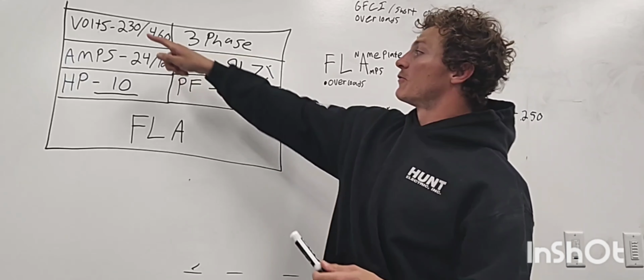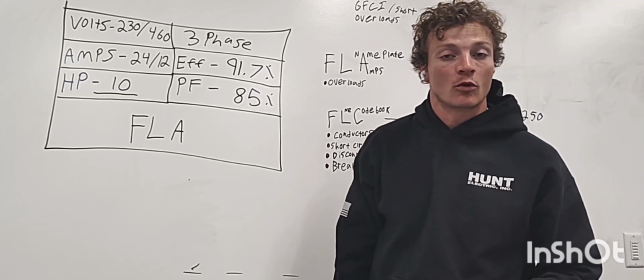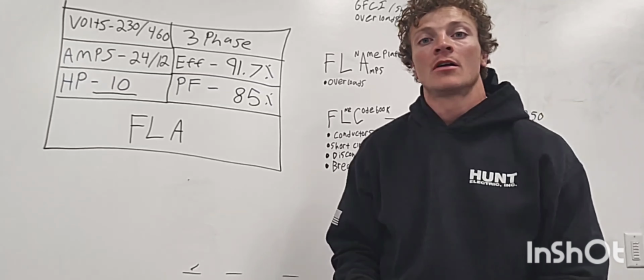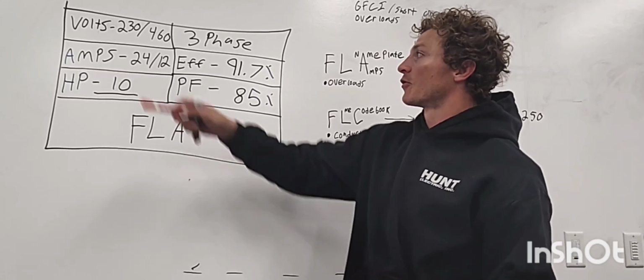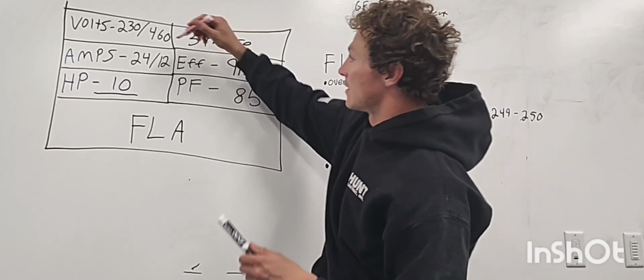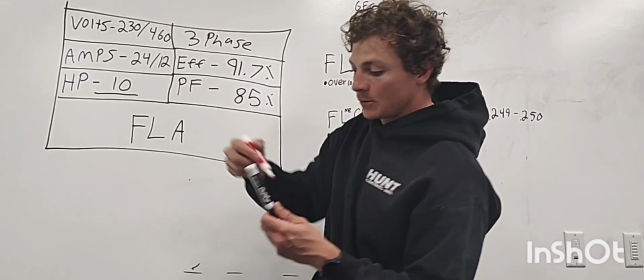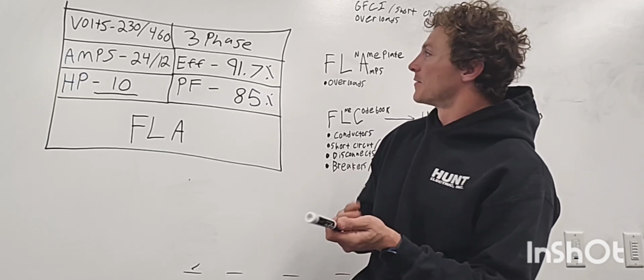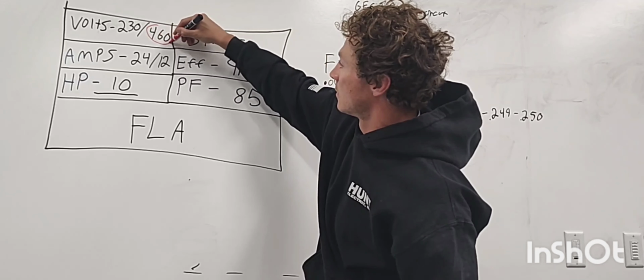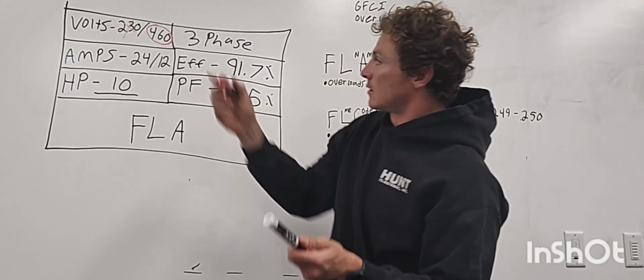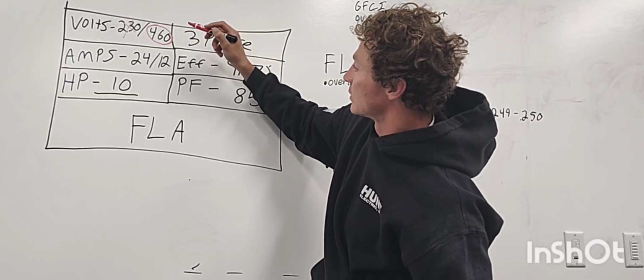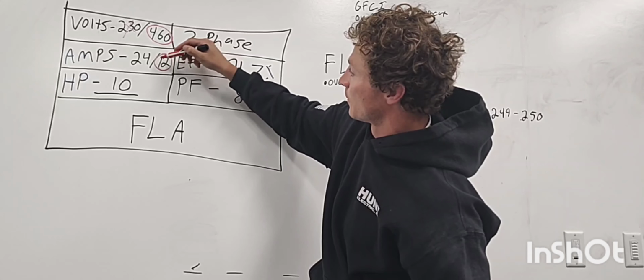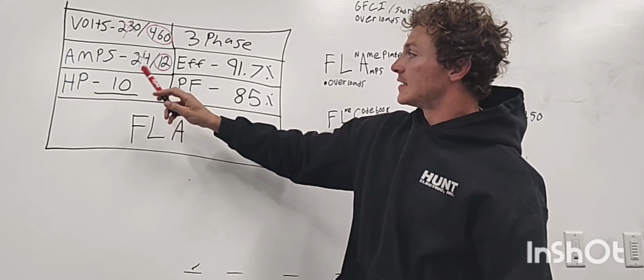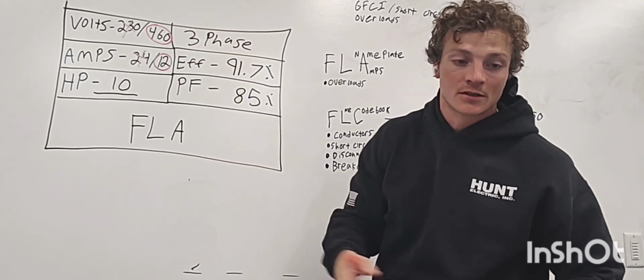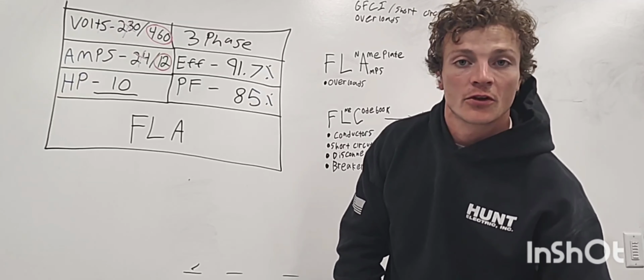Now remember, the voltage and the amps were different depending on what it was tapped for. So, if I remember correctly, it was tapped for the higher voltage. So we're going to use this voltage right here. And we are going to use this amperage. Now, 10 horsepower, doesn't matter to the voltage, that's what the horsepower is rated at. Let's go in the code book and see what that's rated at.